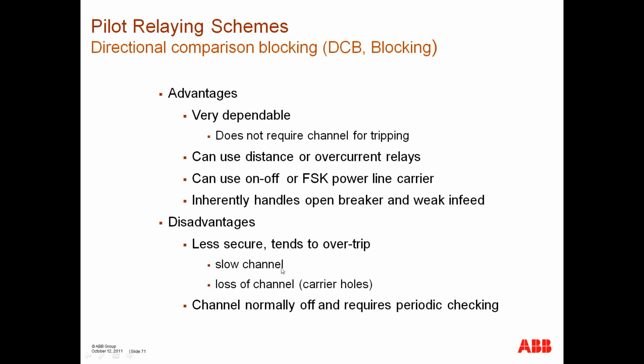If the channel is slow for some reason, if somebody leaves the channel switched off after maintenance. You also have a condition due to poor maintenance of the tuner equipment that produces carrier holes. Channel normally off and requires periodic checking, because the channel doesn't come on until you have an operation. So some people have systems they call check back systems and stuff like that that allows checking the channel once in a while.